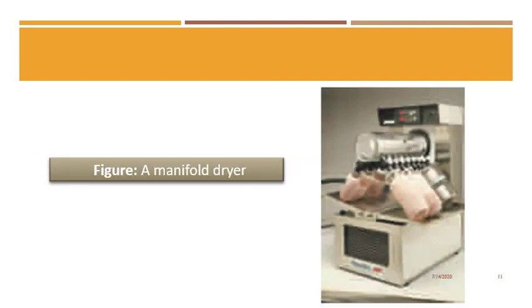And it is a manifold dryer in which pre-frozen samples in vials of different sizes can be attached through ports into the dryer, which supplies a vacuum to remove water.